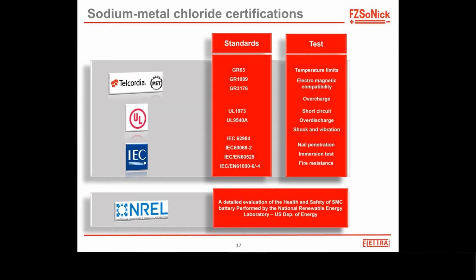As far as testing and certifications, the product has been extensively tested, based not only on industry requirements but new fire codes and building code requirements. In the telecom world we comply with the Telcordia standards and have been tested to the NEBS 3 level. All of our products are UL 1973 and will be covered in our 9540A reporting, which is the large-scale fire testing that UL does.